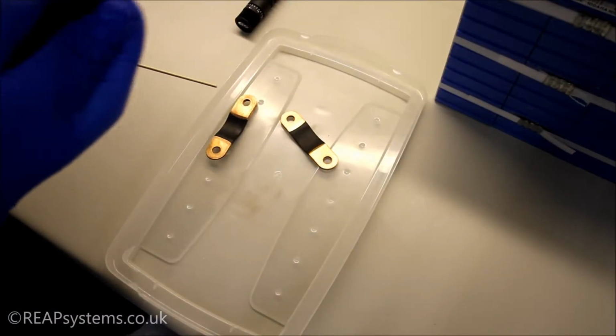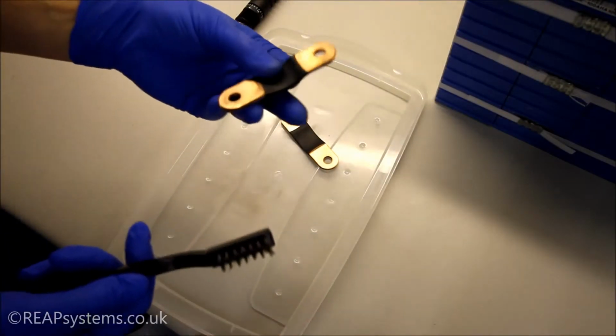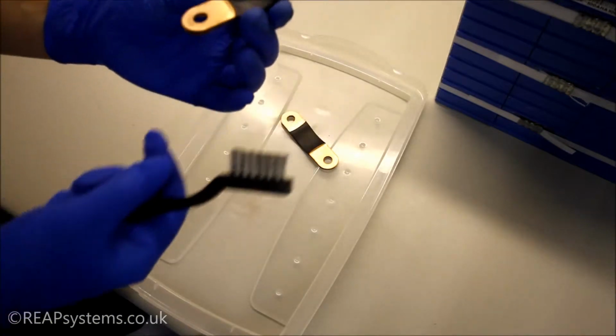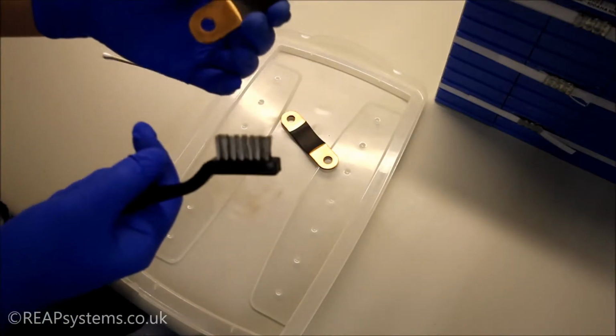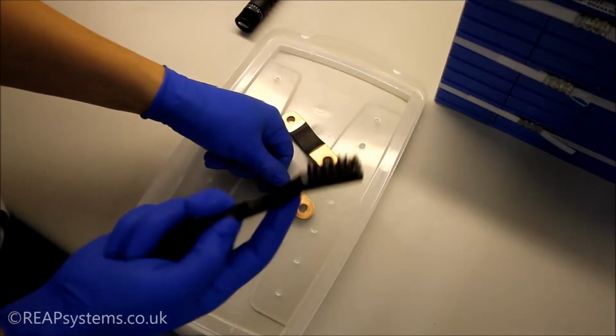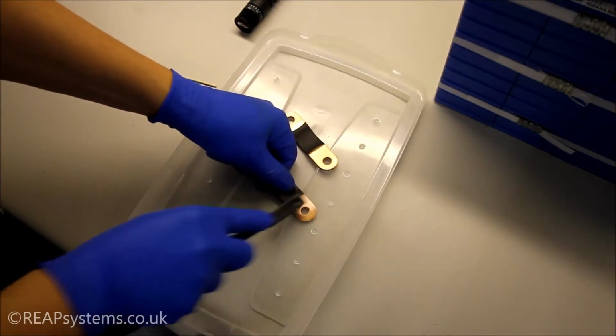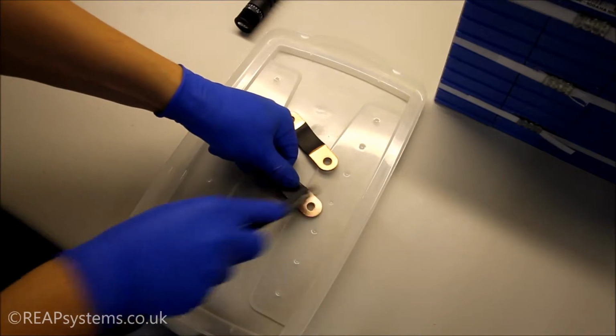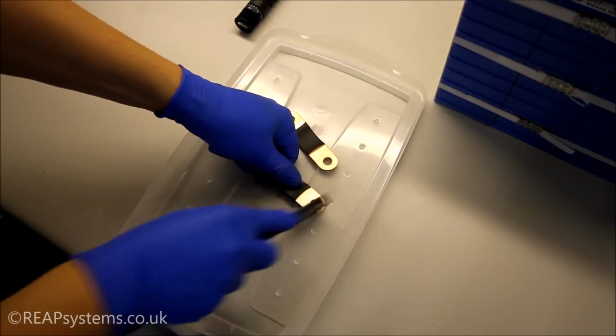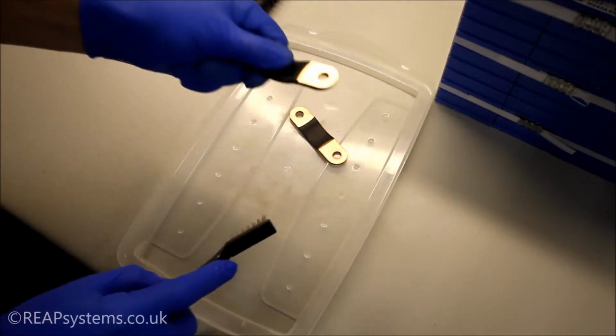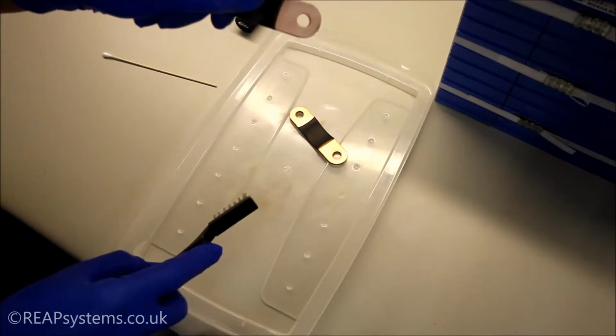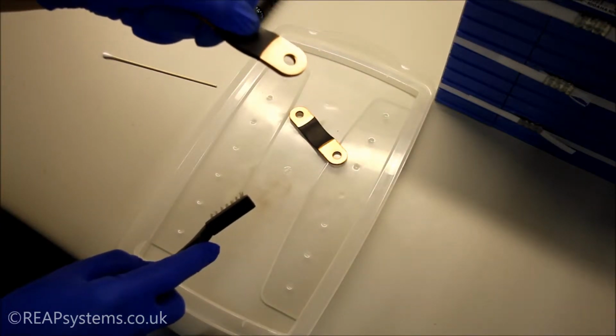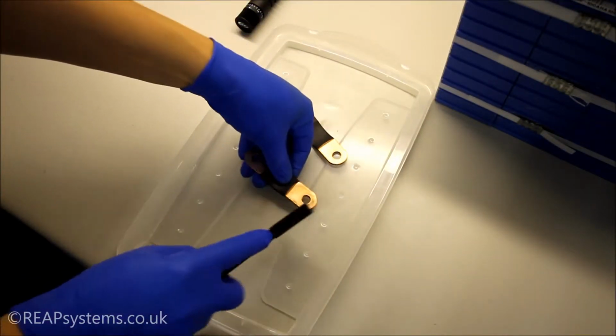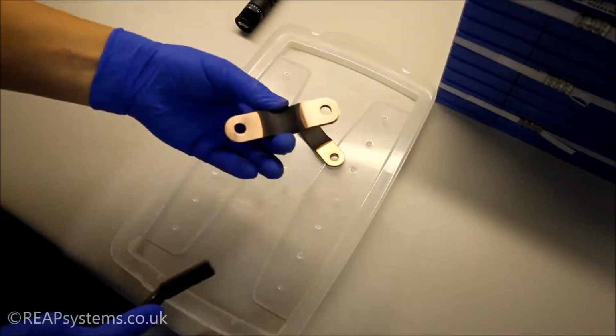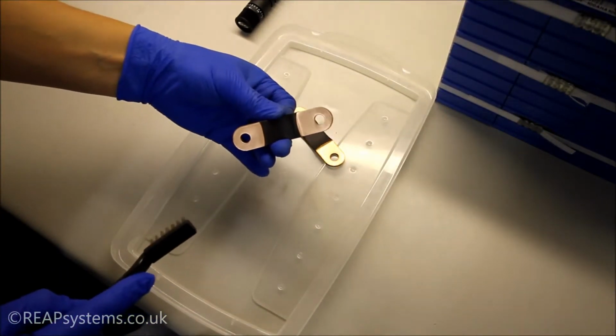We're using a steel bristle brush here, and this is a fairly dirty looking copper bus bar. Take your brush and really start scrubbing quite strongly, but you'll quickly see the difference on the surface there. You've removed all the tarnish. I'll clean another side. Big difference.